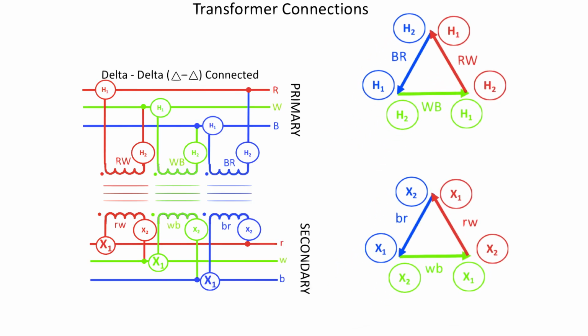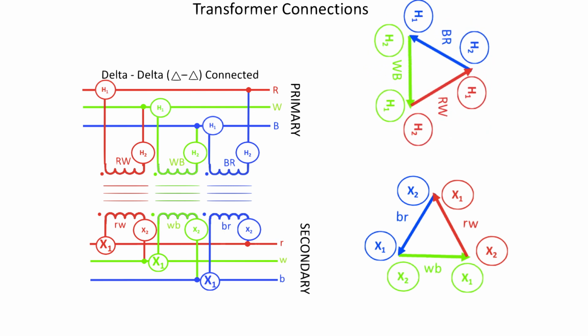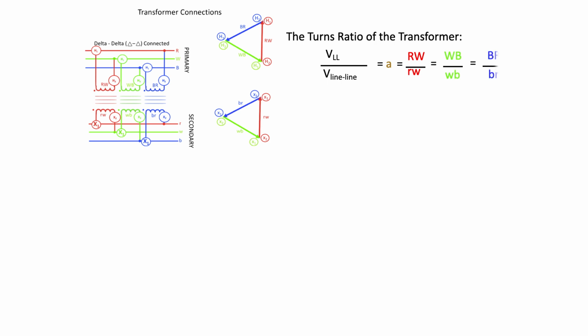I'm going to move everything slightly here and shrink it down so that I can fit some equations on the slide while looking at the diagram at the same time. And I've rotated the phasors slightly, which I'm allowed to do as long as I maintain their relativity. For a delta-delta connected transformer, the turns ratio is given by the primary phase-to-phase voltage over the secondary phase-to-phase voltage. That is because the phase-to-phase voltages bridge the entire coil of each of the transformer legs.